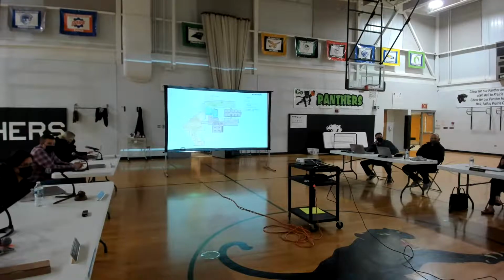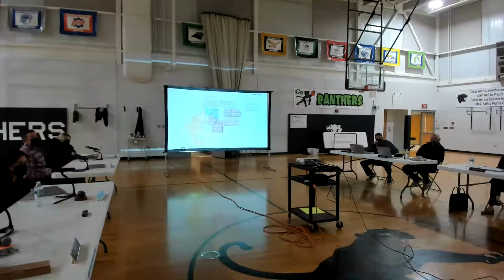There are many different ways to create a geothermal system. What could potentially have happened is the power went out, so he no longer had power to the system. Just like you have now with a generator, you have to have a backup power solution to run the pumps in the well field, bringing the fluid through the building. As long as the power is out, you need that system running, you want that fluid moving through the building constantly. If the power goes out, you still want those pumps working, so typically the backup power would be extended to the system that pumps it through the building.